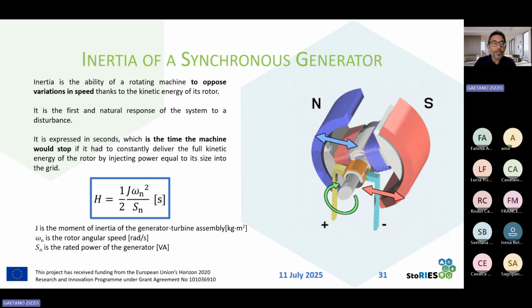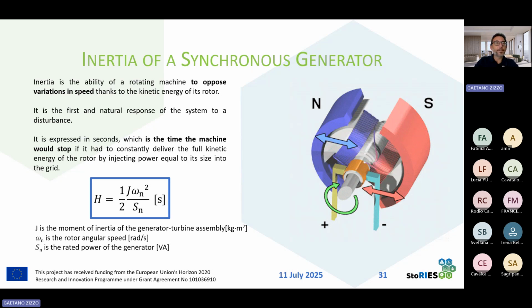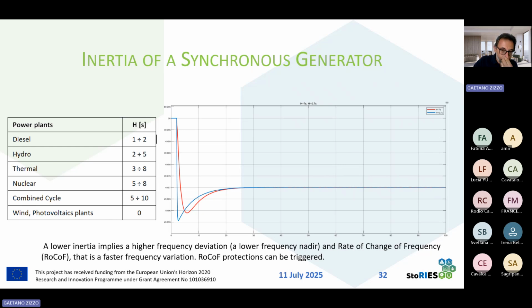Due to the decommissioning of various thermal power plants, the inertia of the whole electrical system worldwide is reducing over the years. So we need to replace this inertia, and we can do this thanks to storage systems. Why is it important to not reduce the inertia? As you can see from this figure, where we have simulated the same system with an inertia of 7 seconds and with an inertia of 0.7 seconds, the system with the inertia of 7 seconds after the disturbance reaches a new value of frequency, but with a frequency nadir that is higher than that of the system with 0.7 seconds inertia.